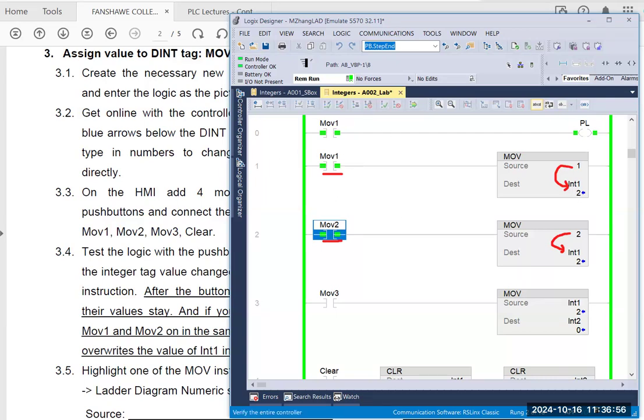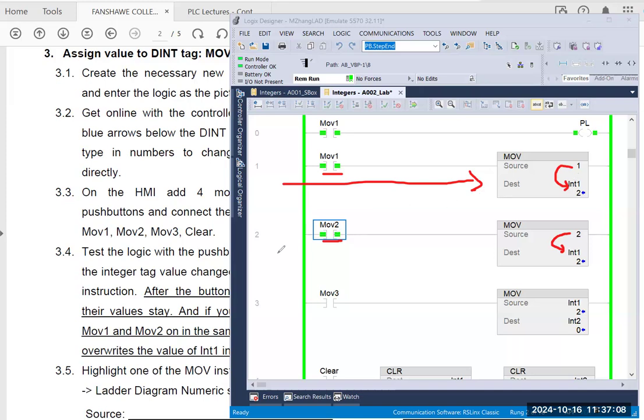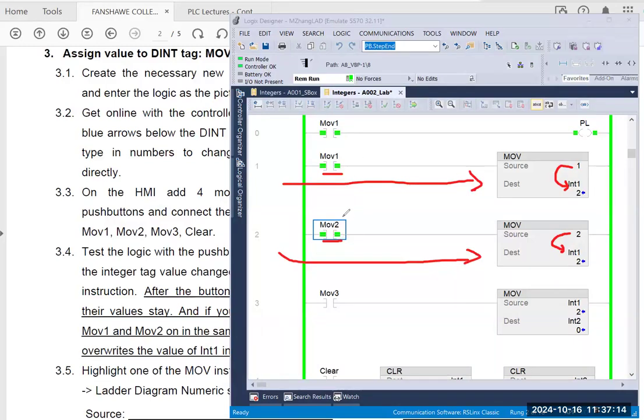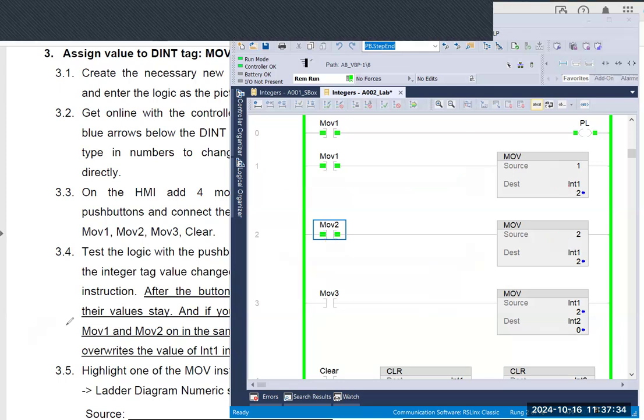Because with PLC scanned, it will scan rung one first, assign the value 1 into INT1 only briefly at that period of time. Because right after, PLC will start to scan the second, the rung two. And then because both triggers are true, the value 2 will override the previous value 1. That's why you only see a value 2. This is just something I want you to realize. This is similar to what we have with the Boolean tag and bit logic. So this is the first demo for today.